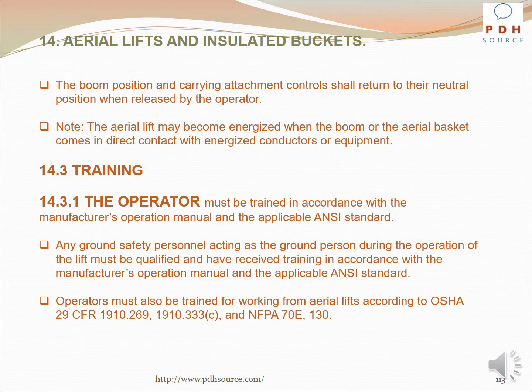Note: the aerial lift may become energized when the boom or the aerial basket comes in direct contact with energized conductors or equipment. The operator must be trained in accordance with the manufacturer's operation manual and the applicable ANSI standard. Any ground safety personnel acting as the ground person during the operation of the lift must be qualified and have received training in accordance with the manufacturer's operation manual and the applicable ANSI standard. Operators must also be trained for working from aerial lifts according to OSHA 29 CFR 1910.269, 1910.333(c), and NFPA 70E and 130.